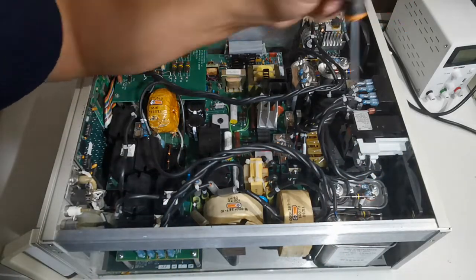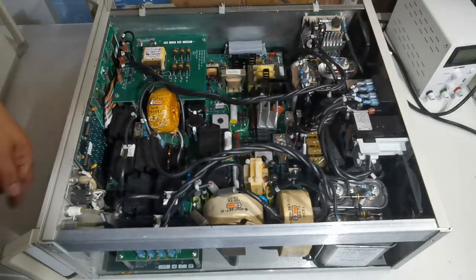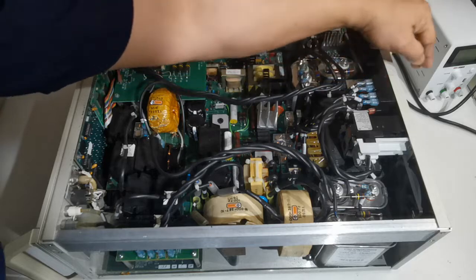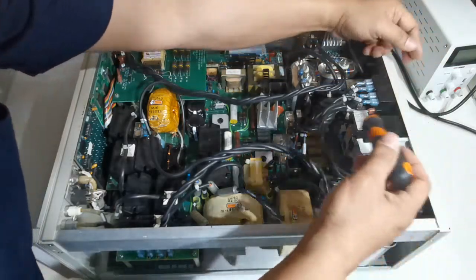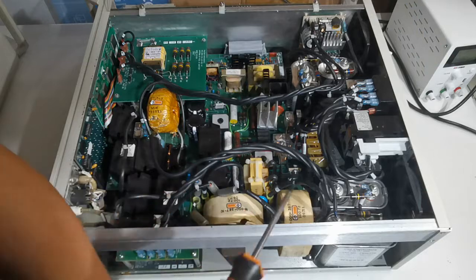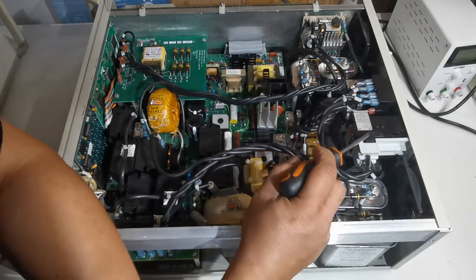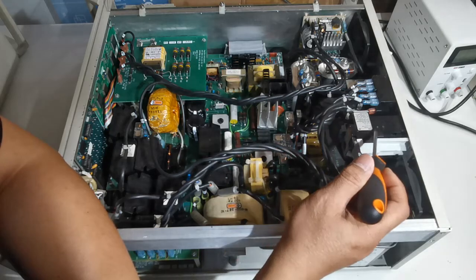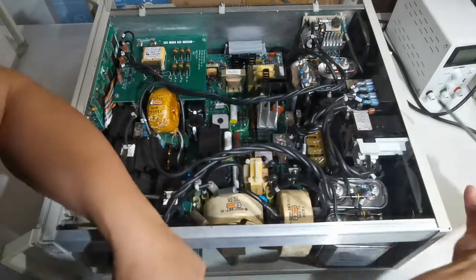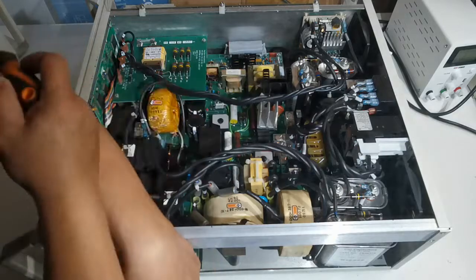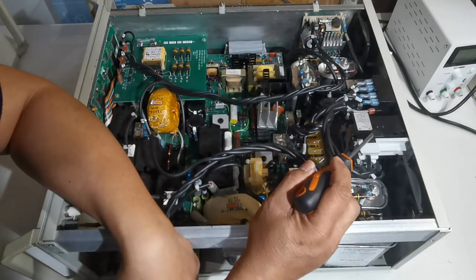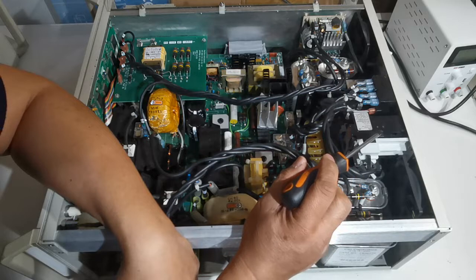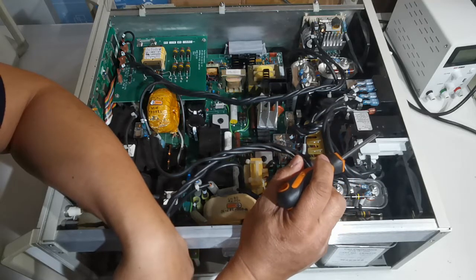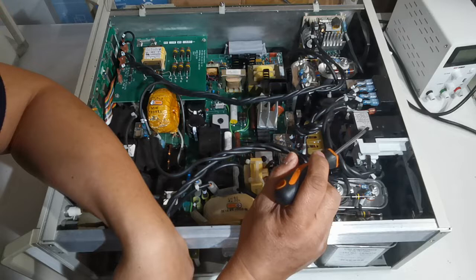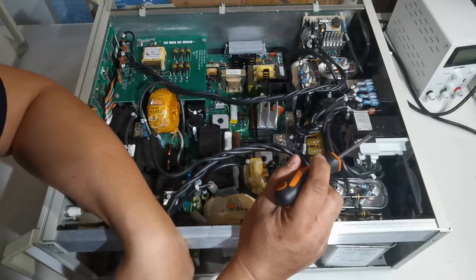So this is the relay for the surge. When you turn on the surge on the front, EUT on the front, this will activate the relay, allowing the EUT power to pass through the front of this system. This one here is the big contactor, which is also coming from the EUT power from the mains. The other unit has a different contactor, which is rated only up to 10 amps or 125 volts maximum. This is rated up to 240 volts, 16 amps.